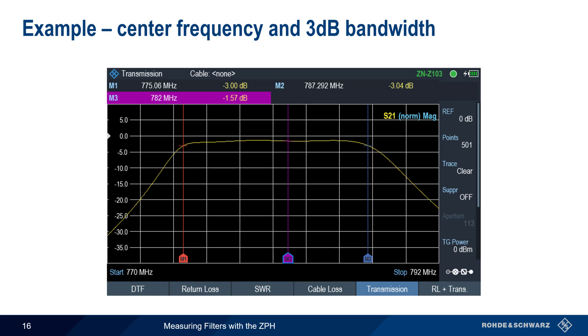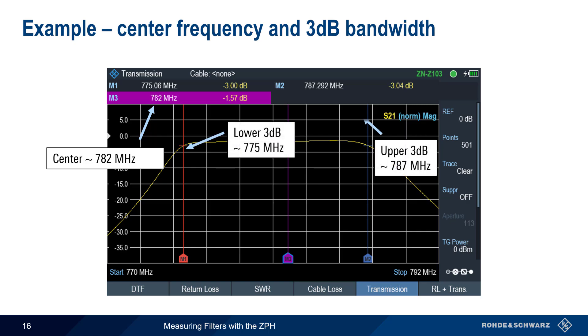Let's use markers to make some basic filter measurements. We've placed three markers: one on the center frequency of our filter pass band, here approximately 782 MHz, and one each on the lower and upper 3 dB points, which is how filter pass band is normally specified. Looking at the difference between these two 3 dB points, we can calculate the pass band of our filter as being approximately 12 MHz.